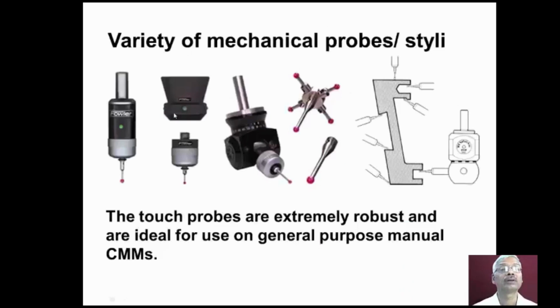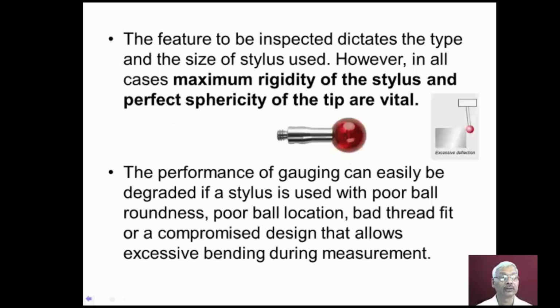I can see these pictures show a variety of mechanical probes. The motorized probe wherein the angle can be changed, star type probe heads are possible, motorized probe head wherein the angle can be adjusted depending upon the workpiece type. These touch probes are extremely robust, and they are ideal for use on general purpose manual coordinate measuring machines. The feature to be inspected dictates the type and size of the stylus used.